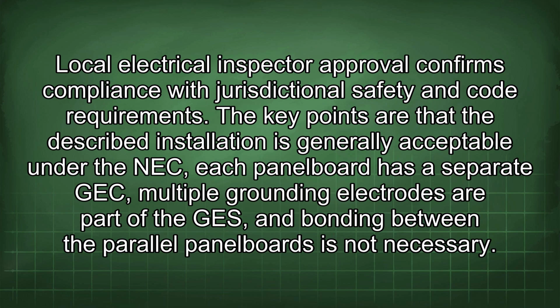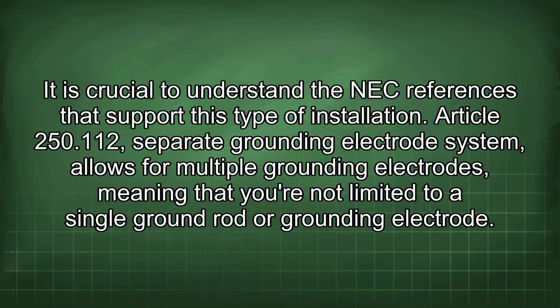The key points are that the described installation is generally acceptable under the NEC. Each panel board has a separate GEC, multiple grounding electrodes are part of the GES, and bonding between the parallel panel boards is not necessary. It is crucial to understand the NEC references that support this type of installation.